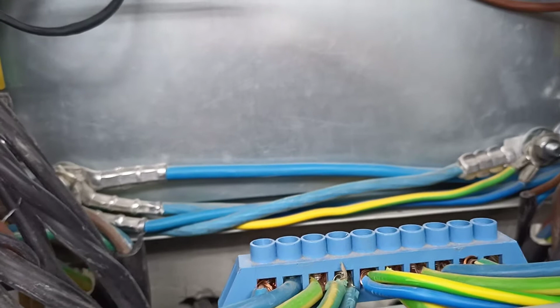So this is the DC part, and here is the AC part, the AC1 connection. I use a 6 millimeter cable, and we have first the neutral, then the phase, the brown one, the hot cable, and we have ground. And the cable comes here.